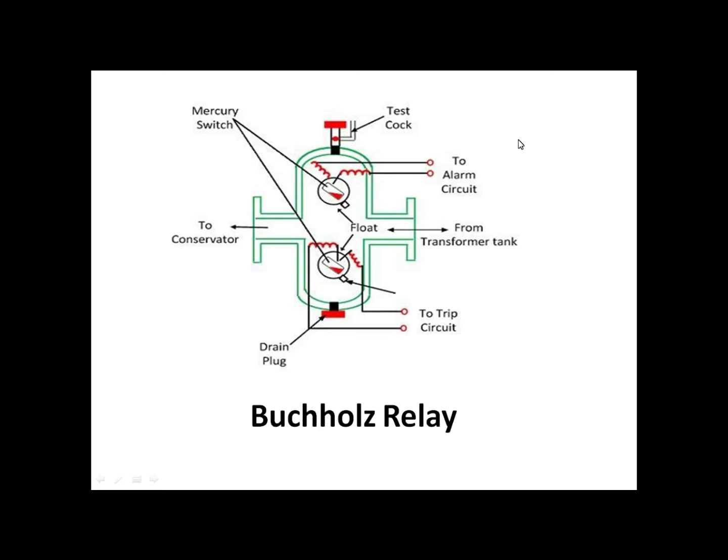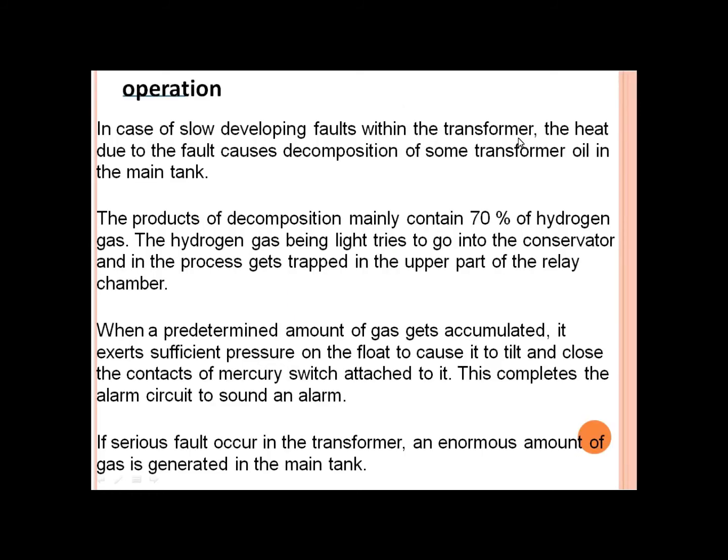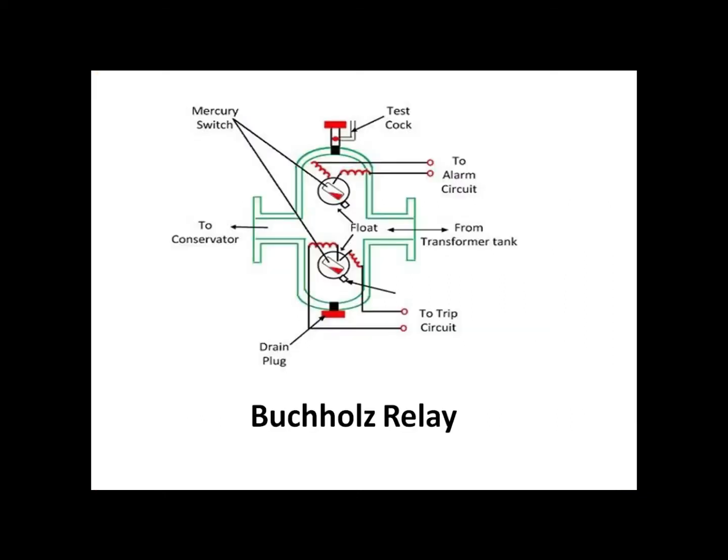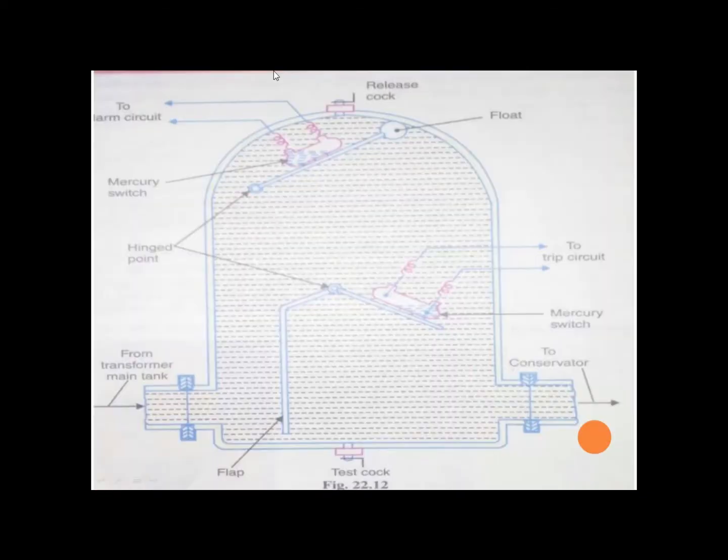If we discuss the operating principle, what happens? In case of a slow developing fault within the transformer, the heat due to the fault causes decomposition of some transformer oil in the main tank. So if you have a fault that occurs, when the oil breaks down, gases are produced.